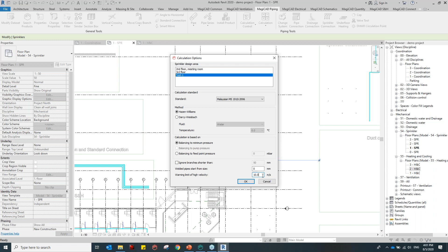Here also there are no restrictions, and you can also specify the warning limits. If the velocity increases more than 10 meters per second, as per the Malaysian standards and BOMBA regulations, you cannot exceed 10 meters per second velocity. So you can set a warning limit so that if your pipe or your flow exceeds 10 meters per second in the sprinkler calculations, you actually get a notification that the velocity is at maximum. Then you can look for alternative options. That's also possible. For example, just click OK.